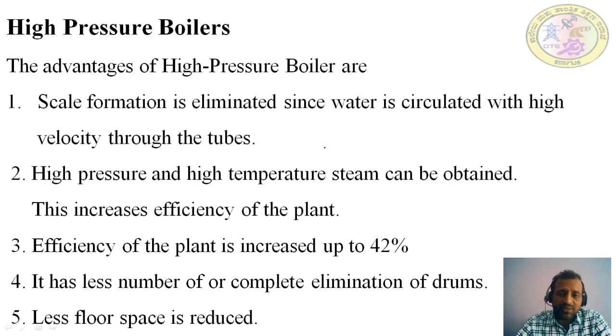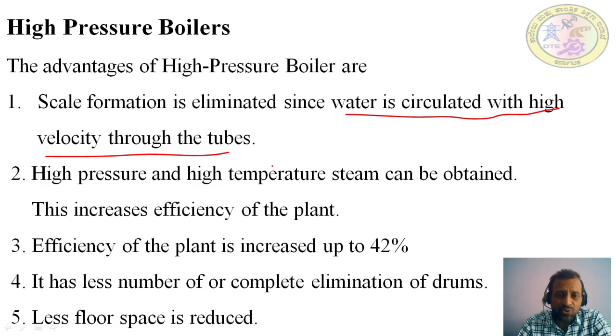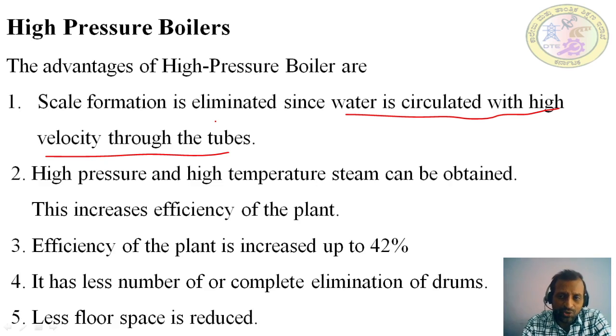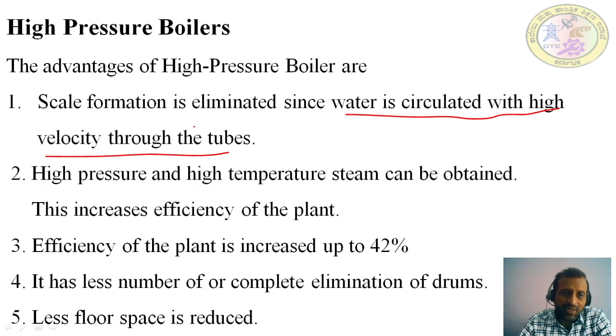In a high pressure boiler, water is circulated with high velocity through the tubes. When water flows at high velocity, deposition of impurities on the inner surface of the tubes does not happen. In the high pressure boiler, water is fed inside the tubes with the help of a centrifugal pump — this is forced convection. Because the velocity is high, the time available for impurities or sediments to deposit is not sufficient, so deposition is completely avoided.